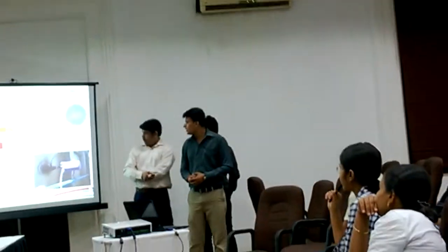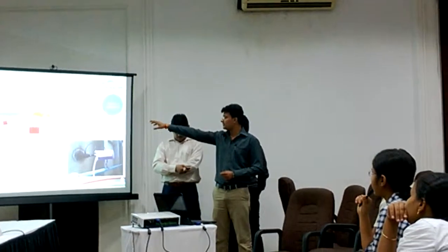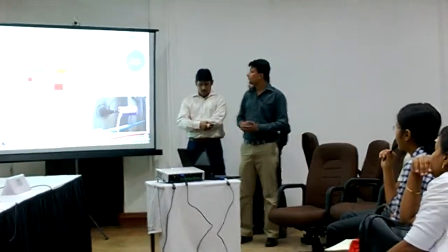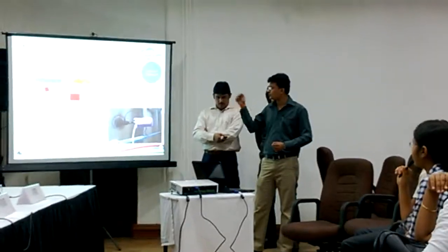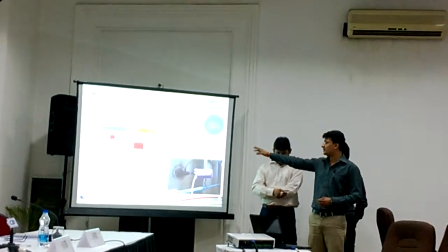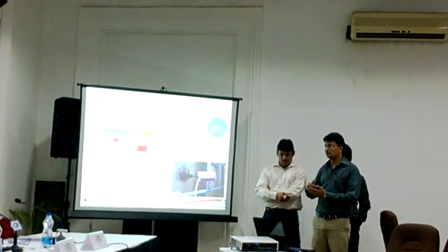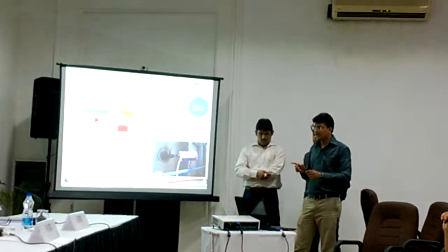Now let's come to the modification part. We have extended the sensing tube of the backside burner flame scanner, so that when the fumes are coming, they don't block the path of UV rays from the flame to the sensor. And the flame scanner on the side wall, we made perpendicular to the flame so that it can see the flame in a broad way.